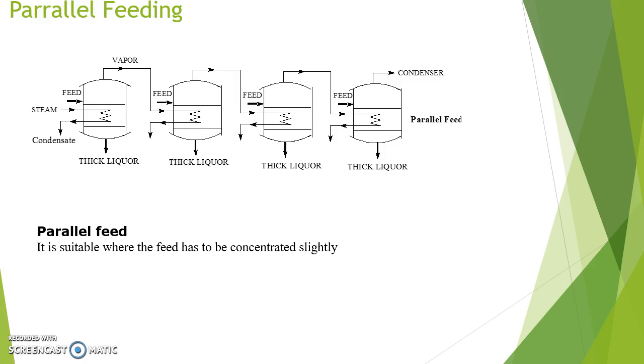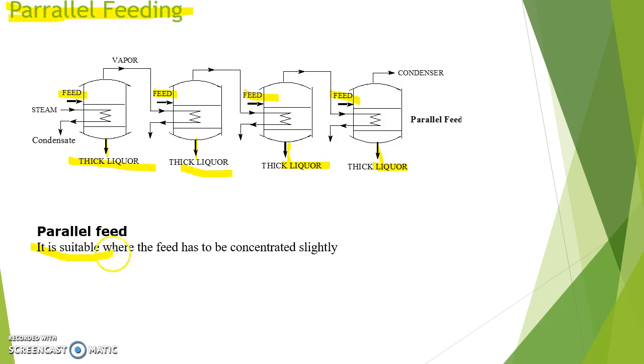The last method is parallel feeding. In parallel feeding, feed is supplied to all effects — first, second, third, and fourth — separately, and the product is also collected as thick liquor from all the effects. This method is suitable for feeds that need to be concentrated only slightly, meaning it should be used in cases where a less concentrated product is necessary. This covers evaporation, its objective, the multiple effect evaporator, and its feeding arrangements.